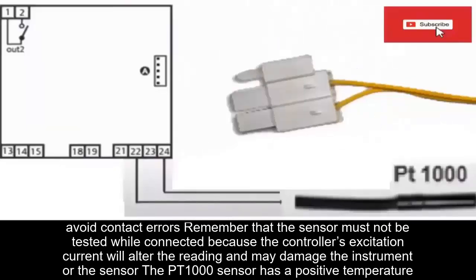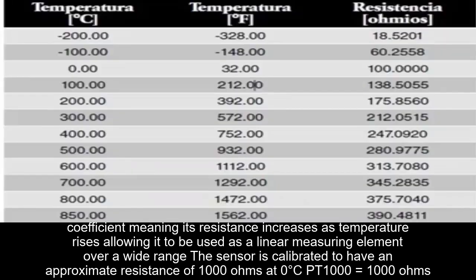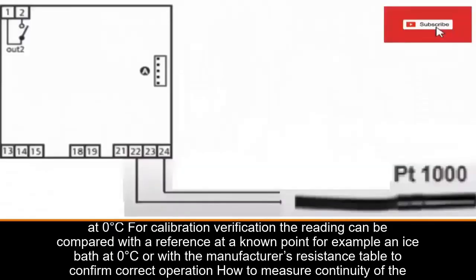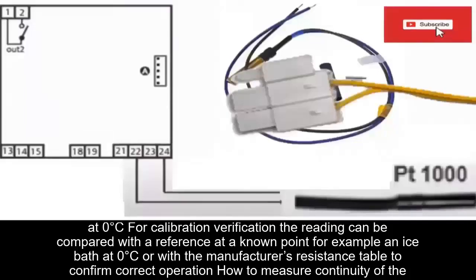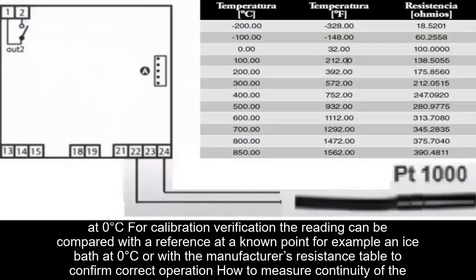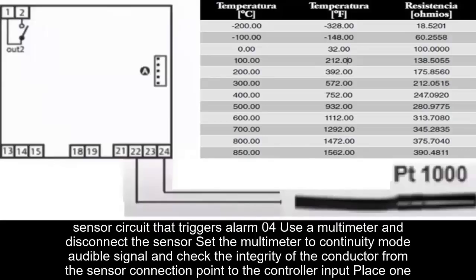The PT1000 sensor has a positive temperature coefficient, meaning its resistance increases as temperature rises, allowing it to be used as a linear measuring element over a wide range. The sensor is calibrated to have an approximate resistance of 1000 ohms at 0 degrees Celsius. PT1000 equals 1000 ohms at 0 degrees Celsius. For calibration verification, the reading can be compared with a reference at a known point, for example, an ice bath at 0 degrees Celsius, or with the manufacturer's resistance table to confirm correct operation.